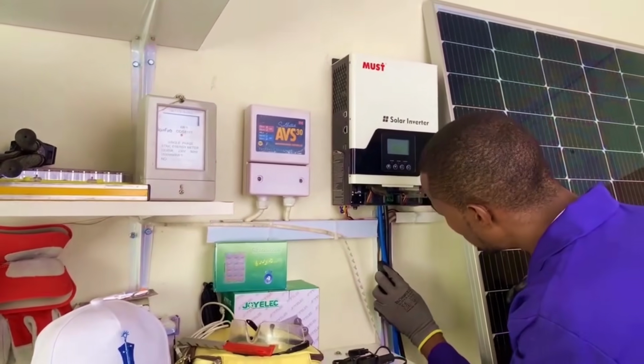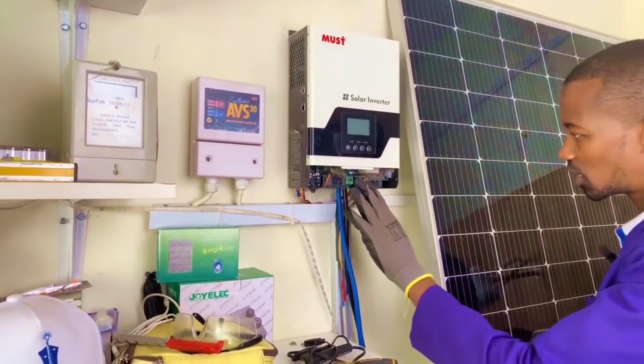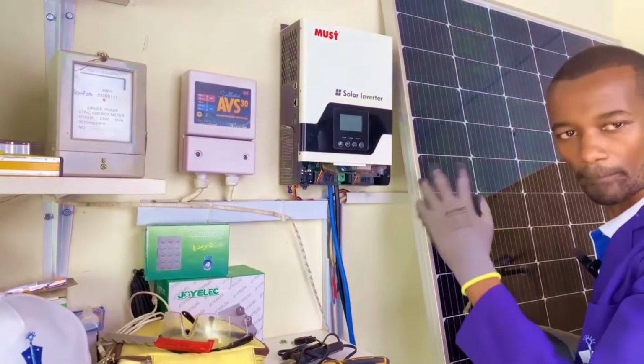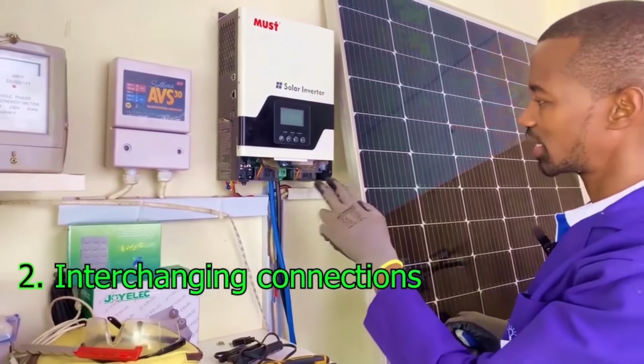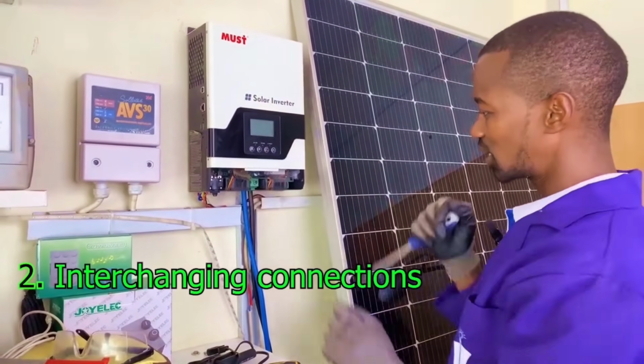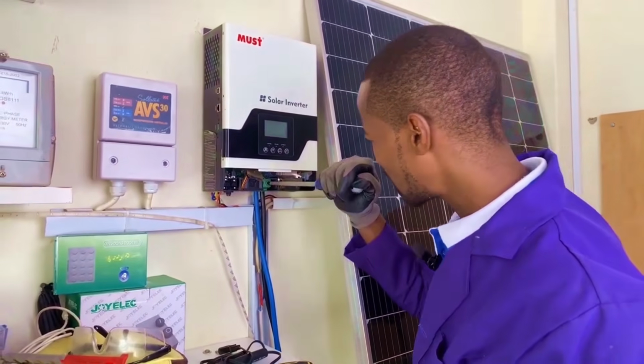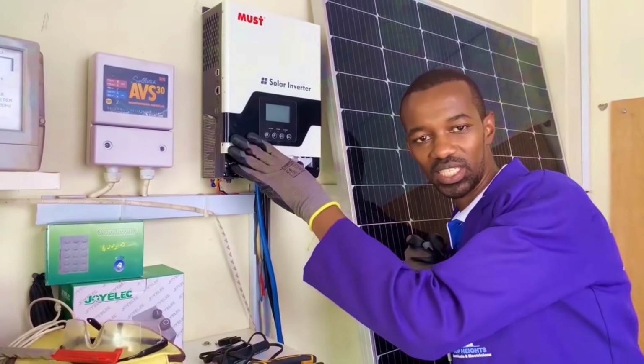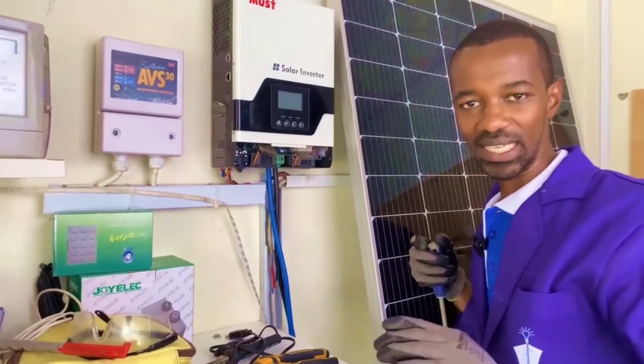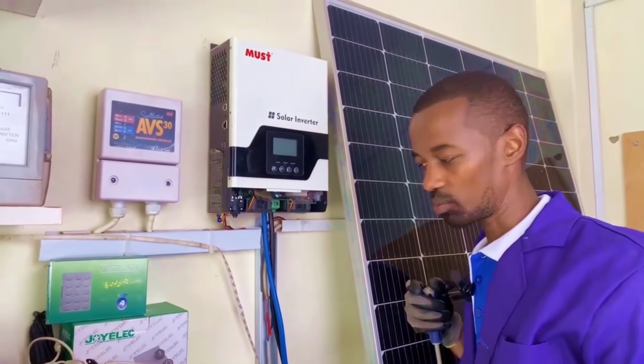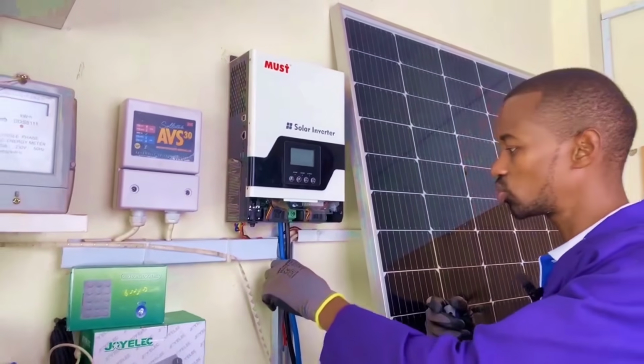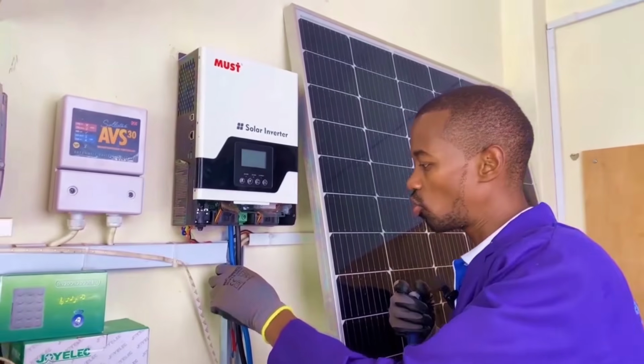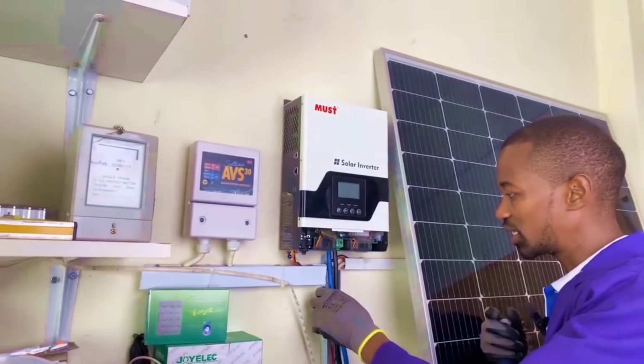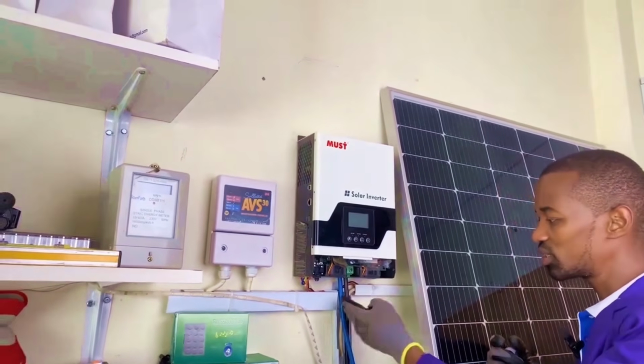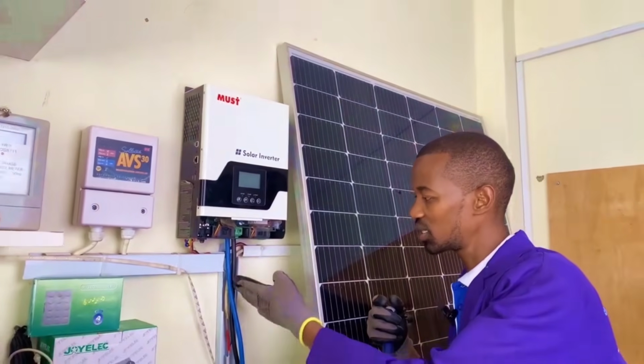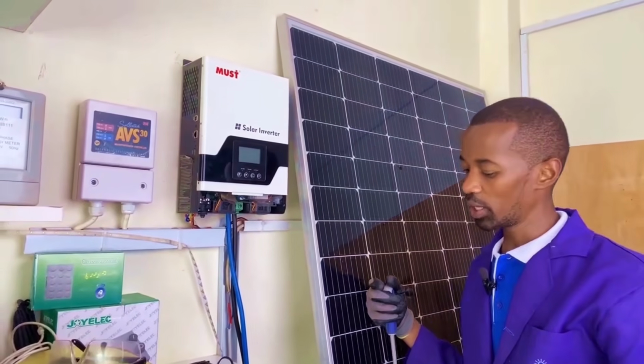So the first mistake that we have said is interchanging the connection. Positive, you connect to negative, and negative to positive. That definitely can damage the inverter. Another mistake that people commit when it comes to installation of an inverter is using undersized cables. For instance, if you decide to use very low size or very small sized cables, if you decide to use 2.5 for these battery cables, they will overheat.